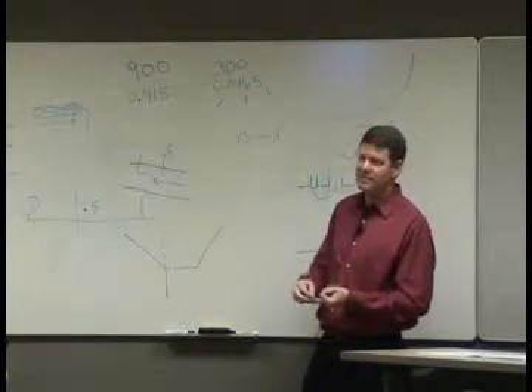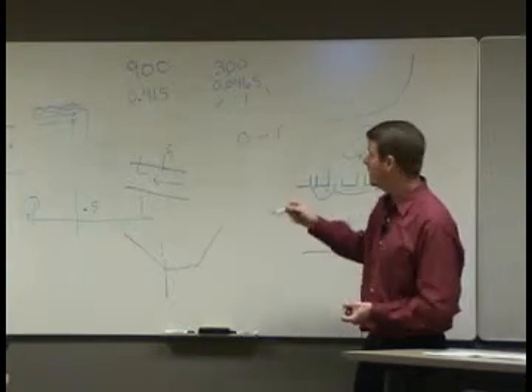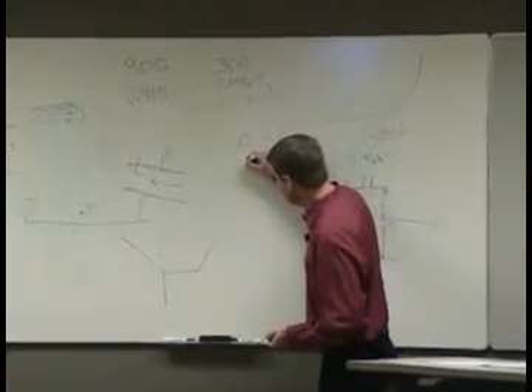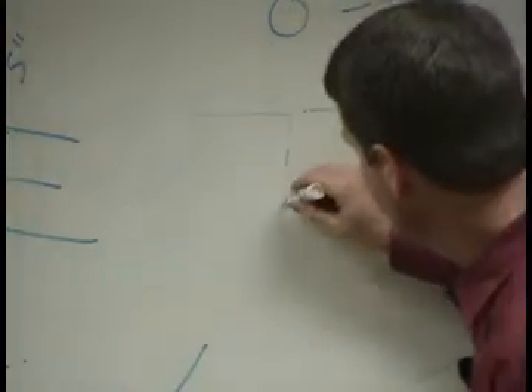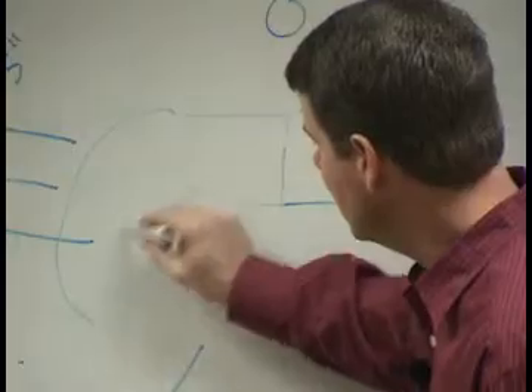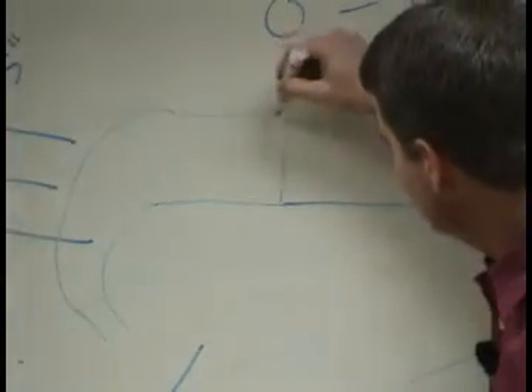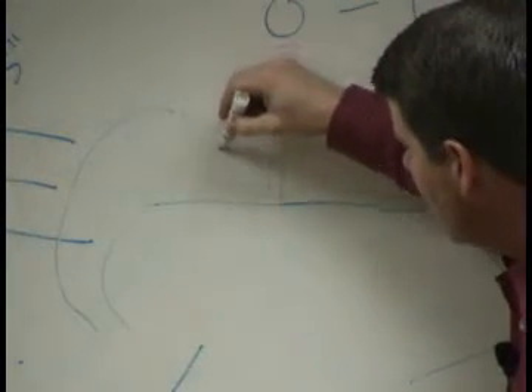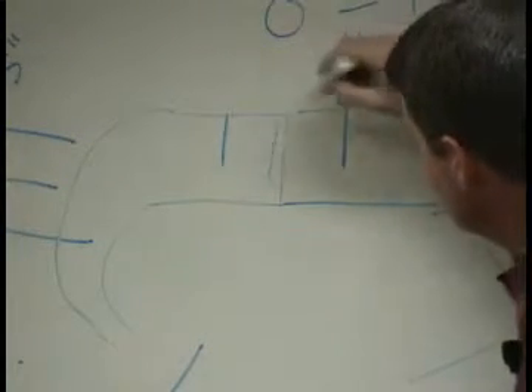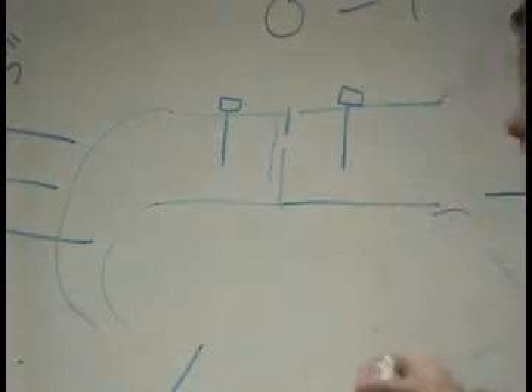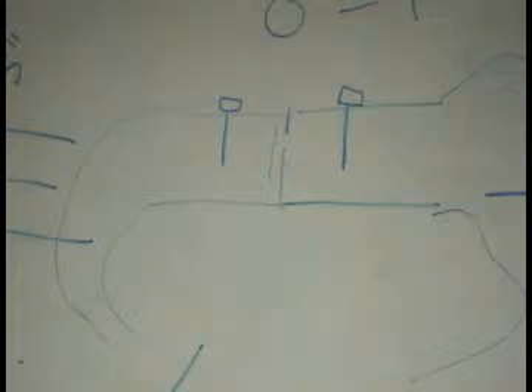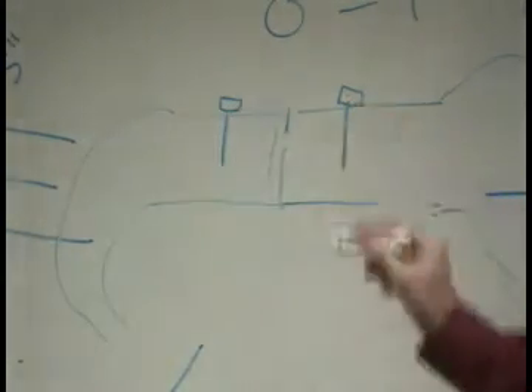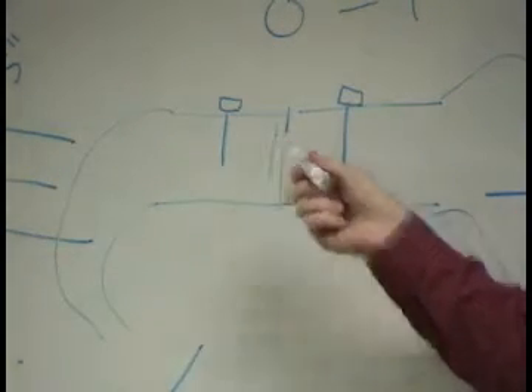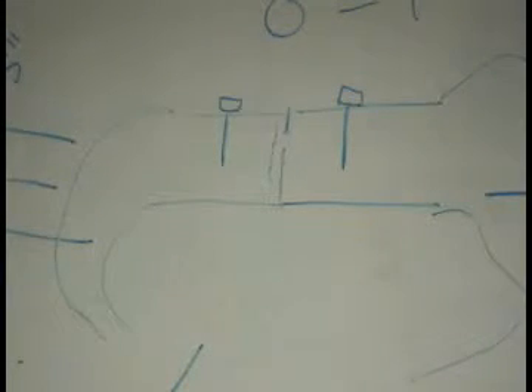Andover uses a hot wire anemometer type of device for their airflow sensor. And what that is, an orifice, you hook your plastic on each end, going off to the two tubes on your pitot here, and they have a tiny heater and a tiny temp sensor and an orifice in there, and they know the exact area of that orifice, and they know exactly how much heat that heater is putting out, and so they measure the difference in temperature and calculate how much air is passing over that heater. That is the way that thing works.